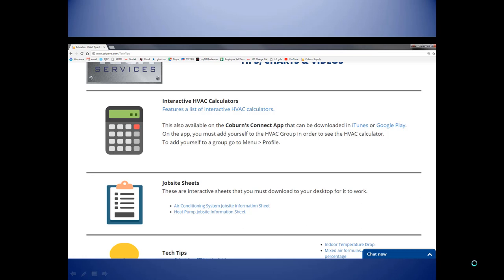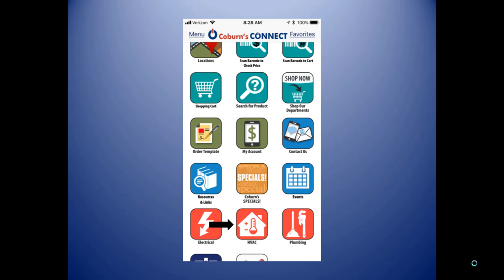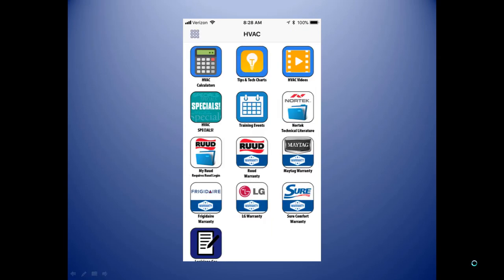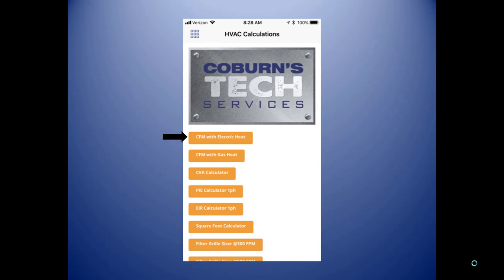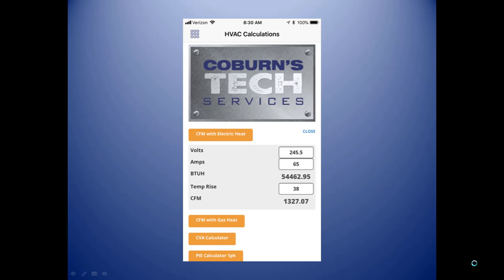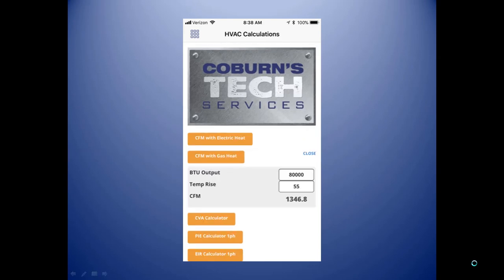You can do that by going to Coburns.com under Interactive Calculators or the Coburns Connect app. Go to Interactive Calculators under the HVAC tab here on the Connect app, and go to CFM with electric. And all you need to do is take the voltage reading with all the heat strips on, and the fan speed in the cooling mode. Also amp readings, and that'll convert your BTUs by using the temperature rise over to CFM. You can do the same thing with the gas furnace chart here. BTU output of the furnace with the temperature rise equals CFM, as you can see here on the chart.